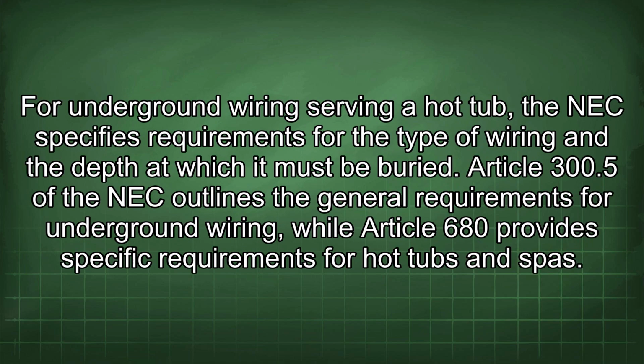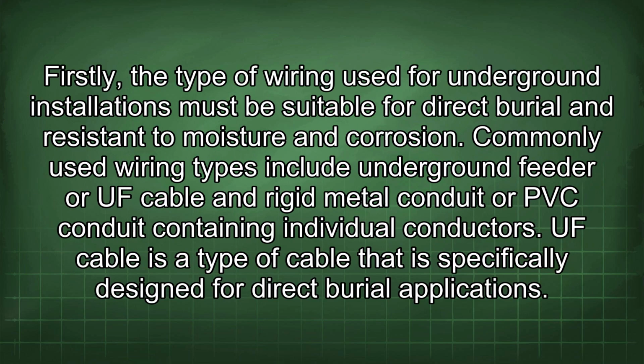For underground wiring to serve a hot tub, the NEC specifies requirements for the type of wiring and the depth at which it must be buried. Article 300.5 of the NEC outlines the general requirements for underground wiring, while Article 680 provides specific requirements for hot tubs and spas. Firstly, the type of wiring used for underground installations must be suitable for direct burial and resistant to moisture and corrosion. Commonly used wiring types include underground feeder, or UF, cable and rigid metal conduit or PVC conduit containing individual conductors. UF cable is a type of cable that is specifically designed for direct burial applications.